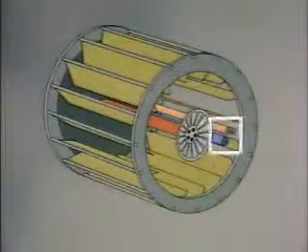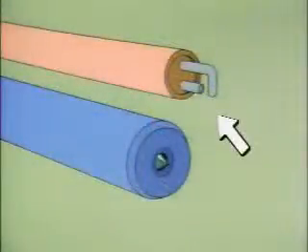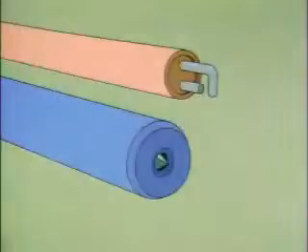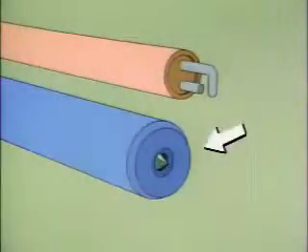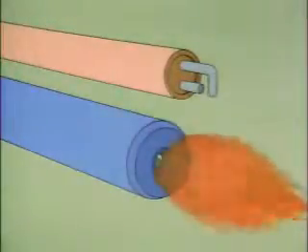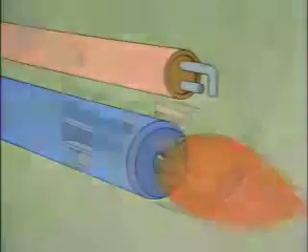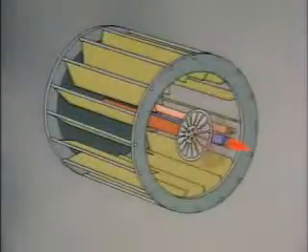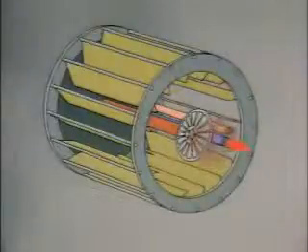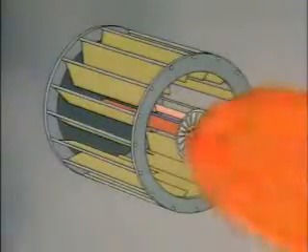To start the oil mist burning there is an igniter, which consists of a sparking device and a separate atomizer serving as a pilot for the burner. A small amount of oil is sent to the igniter atomizer; the oil flows through a nozzle, which creates the mist, and the spark ignites it. After a flame is established at the igniter, oil flow to the main atomizer is started, producing an oil mist, and then the igniter flame ignites the oil mist to begin the combustion process.